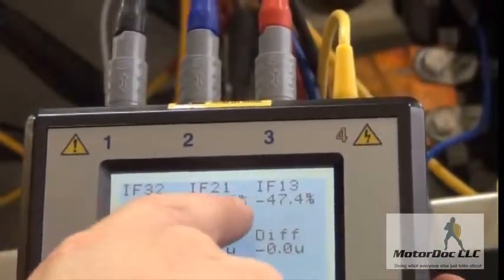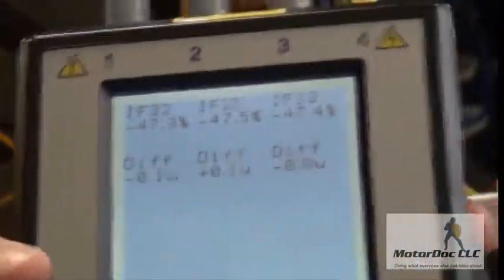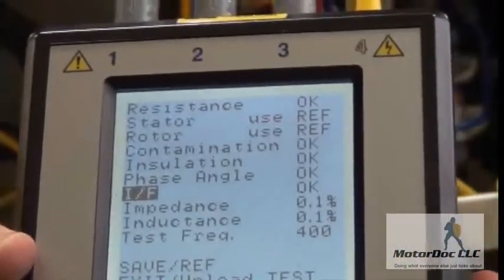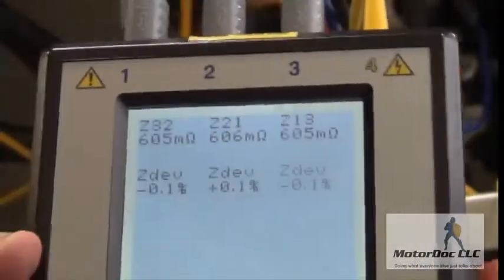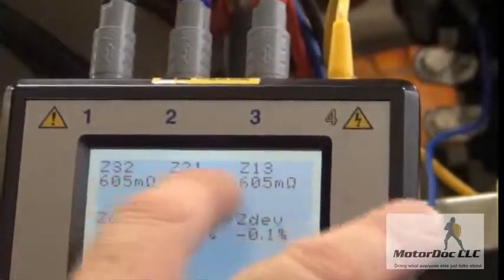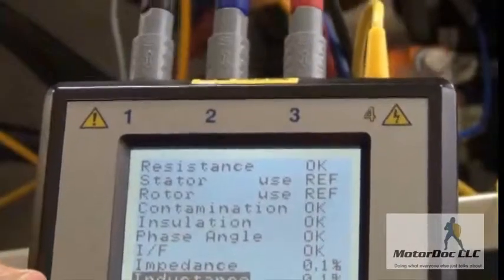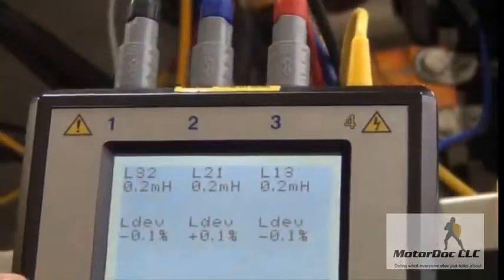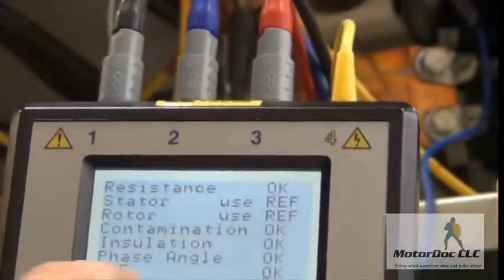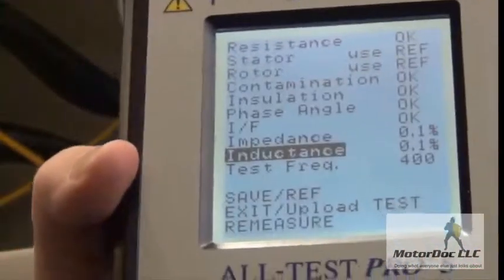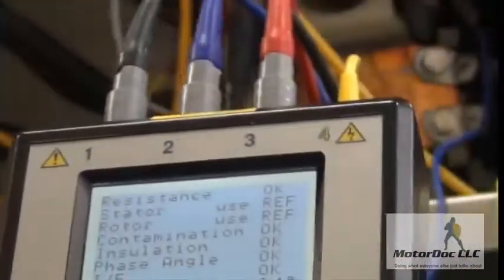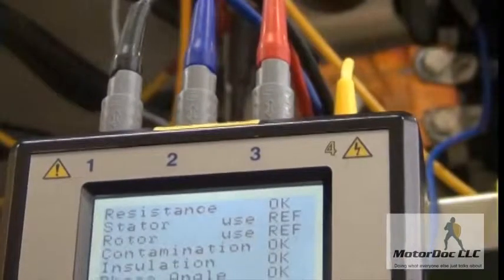Now I go to the I/F test and check: minus 47.3, 47.5, 47.4 - well within the plus or minus one range. Press OK again. I look at the impedance - I was expecting some unbalance, but it shows 605, 606, 605. The inductance is 0.2, 0.2, 0.2 - all good. Last but not least is the test frequency it selected: 400 Hz. I don't have to select that manually. That is now finished.